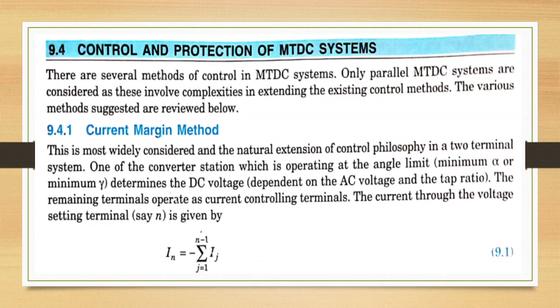One of the converter stations, which is operating at the angle limit minimum alpha or minimum gamma, determines DC voltage dependent on the AC voltage and the tap ratio. Remaining terminals operate as current controlling terminals. Current through the voltage setting terminal, say N, is given as I_N = -Σ(j=1 to N-1) I_j, where N is the number of terminals. In the above equation, inverter currents are treated as negative while the rectifier currents are treated as positive.